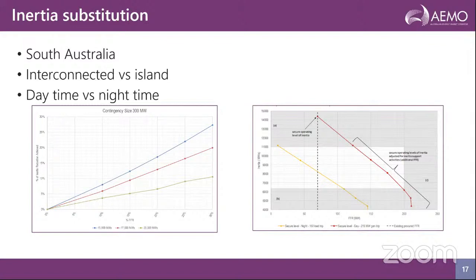Figure on the left is trying to show the relationship between inertia reduction, how much inertia you can reduce as a percentage, and the FFR. And the key message here from the figure on the left is, with other things being equal, the higher inertia substitution can be achieved for low inertia system with increase in FFR. So in a nutshell, the importance of FFR is more noticeable when you have a low inertia grid and your size of the contingency is relatively high.